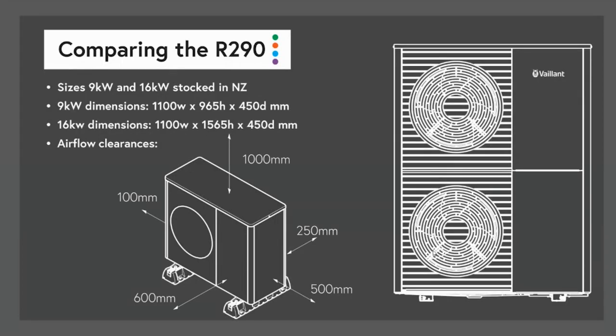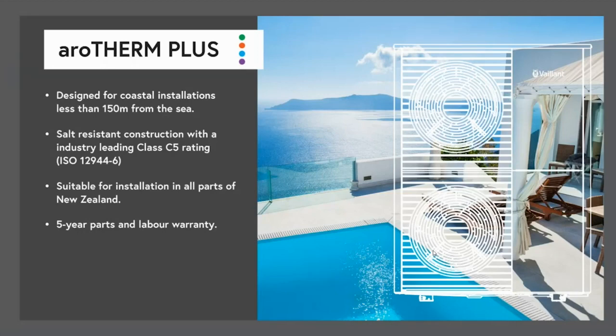In terms of the units, here are the clearances required. It only needs a few 100 millimeters on either side to be installed, so it works on a very small footprint, and we stock the 9 kilowatt and 16 kilowatt sizes in New Zealand. As I mentioned before, it has a very, very high rating. There's the ISO standard it's tested to, and it's got a C5 rating for coastal applications, even less than 150 meters from the sea edge. That means it's suitable for installation in all parts of New Zealand, and it has a 5-year parts and labour warranty.